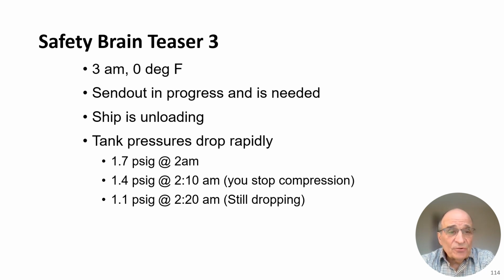Brain teaser number 3. It's again 3 a.m. in the morning, 0 degrees Fahrenheit. Send out is in progress and is needed to supply customers. A ship is unloading and tank pressures drop rapidly. 1.7 psi at 2 a.m., 2:10, 1.4 psi. You stop compression. It's now 2:20 and down to 1.1 psig.